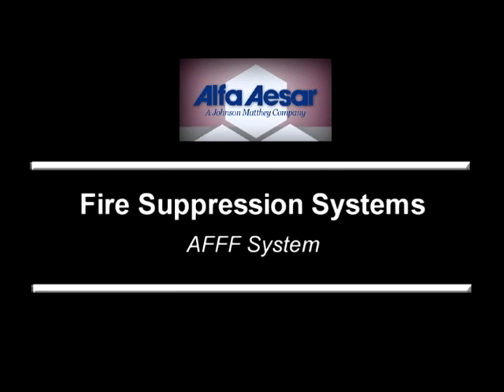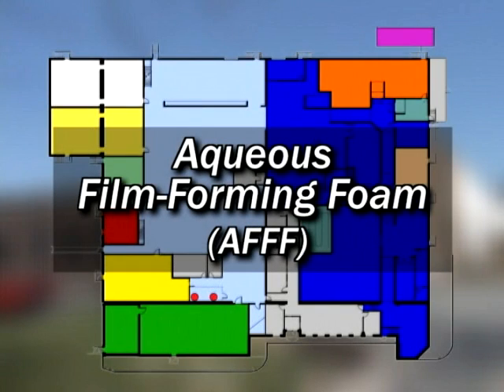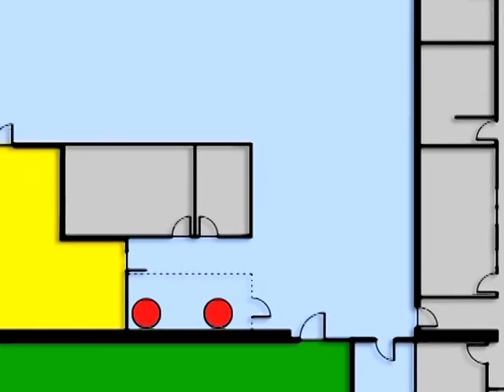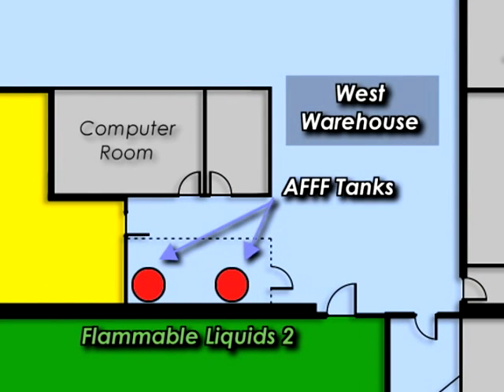AFFF system. An aqueous film-forming foam, or AFFF system, provides coverage for the flammable liquid storage area. The AFFF tank and associated valves are located just inside the west warehouse room, adjacent to the flammable liquid storage area, Flammable Liquids 2. This facilitates shorter foam extinguishing agent release times once a system is activated.